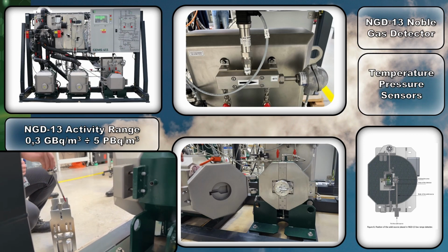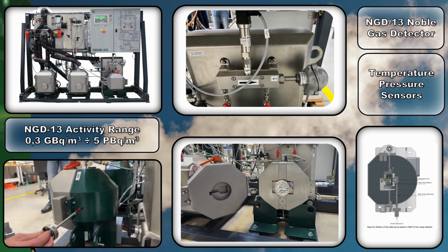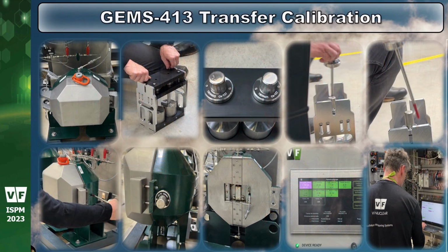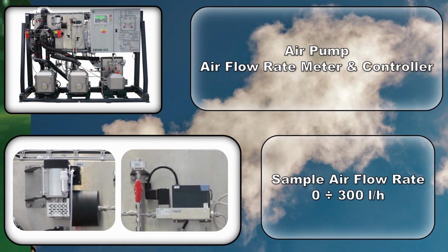Self-absorption correction is applied. The NGD-13 transfer calibration using cesium-137 solid sources is shown on video and on the summary. The air pump and airflow controller are used to provide air sample flow up to 300 liters per hour. Airflow is recalculated to the standard temperature and pressure conditions. Low diameter piping and low sample flow rate are used to reduce total activity in the GEMS-413 parts.